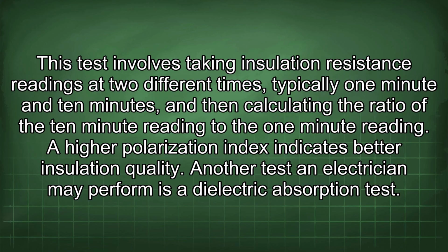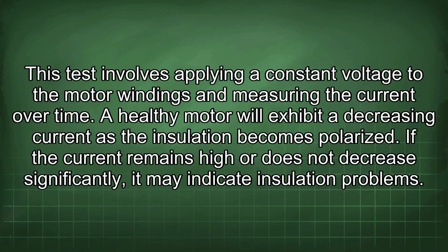Another test an electrician may perform is a dielectric absorption test. This test involves applying a constant voltage to the motor windings and measuring the current over time. A healthy motor will exhibit a decrease in current as the insulation becomes polarized. If the current remains high or does not decrease significantly, it may indicate insulation problems.